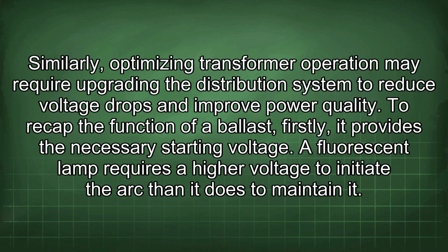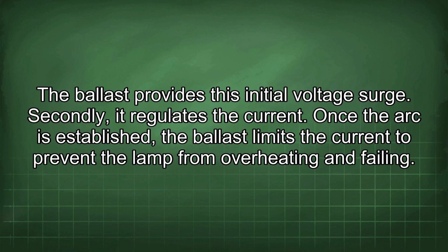To recap the function of a ballast, firstly, it provides the necessary starting voltage. A fluorescent lamp requires a higher voltage to initiate the arc than it does to maintain it. The ballast provides this initial voltage surge. Secondly, it regulates the current. Once the arc is established, the ballast limits the current to prevent the lamp from overheating and failing.